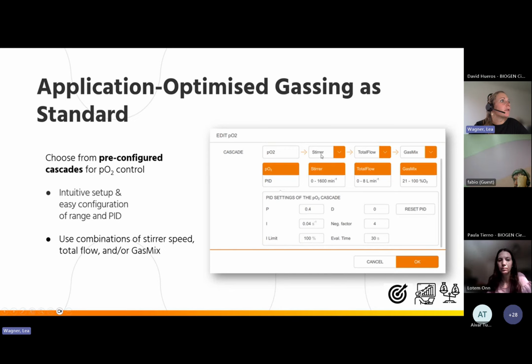the values. So for example, in this case, if the oxygen concentration goes too low, first the stirrer is increased. When the stirrer reaches the set maximum, then the total flow is increased, and then at the end the gas mix. So depending on the application, the customer can choose, maybe for more sensitive cells, to first increase the gas mix and later on the flow and the stirrer. So he has the chance to change the oxygen control depending on the application, which makes the Minifors 2 a very, very flexible product that can be used for different applications and processes.